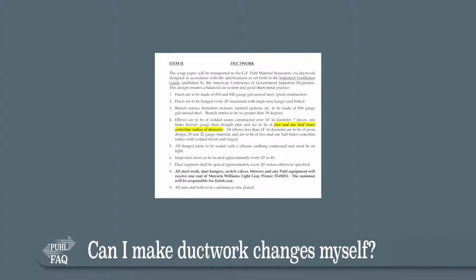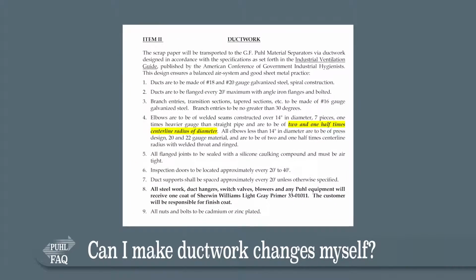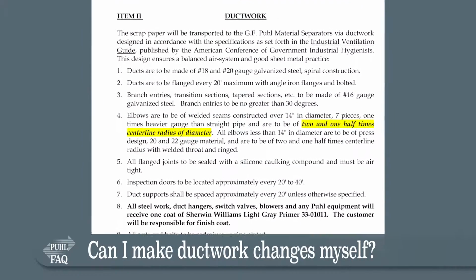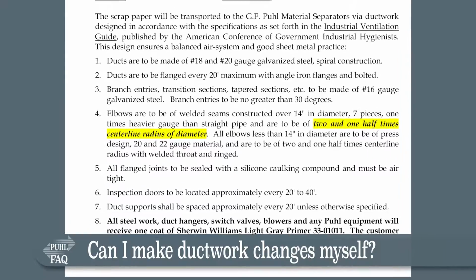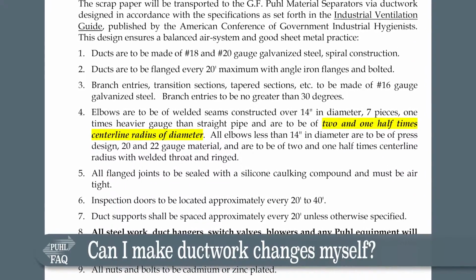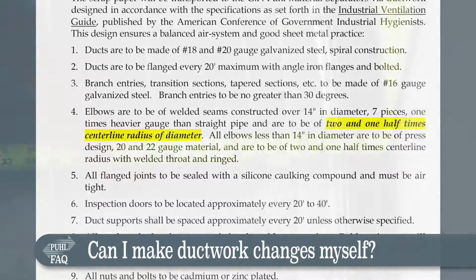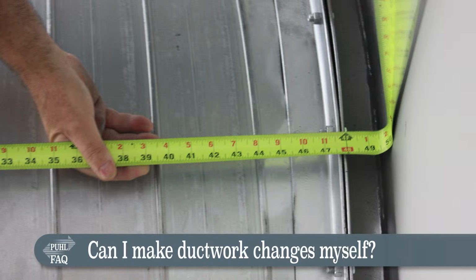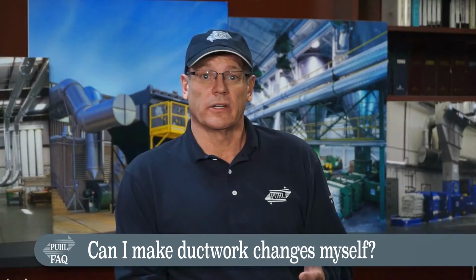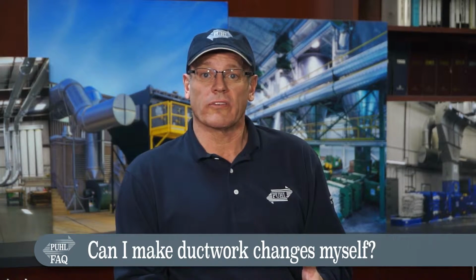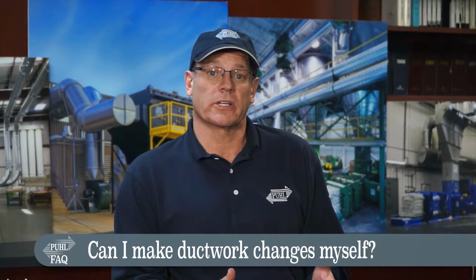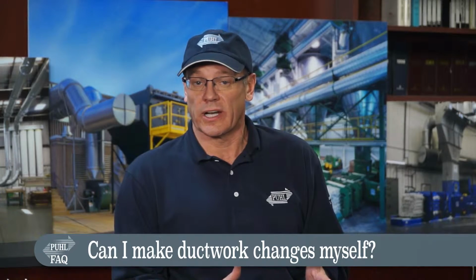Moving materials such as scrap or dust through a duct system is not the same as moving air-conditioned air. The conveying speeds for HVAC system and the duct specifications such as gauge, elbow radius, duct supports, and connections are all very different versus moving material. You're always better off working with a qualified engineer who specializes in moving material through ductwork, not just moving air.